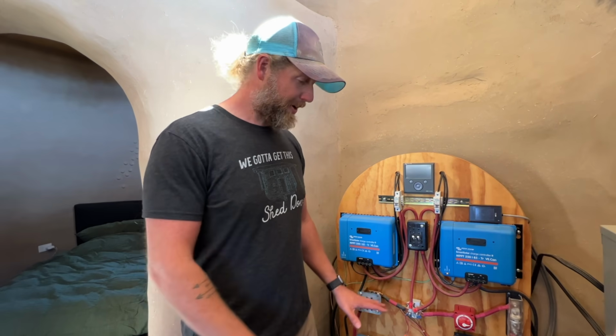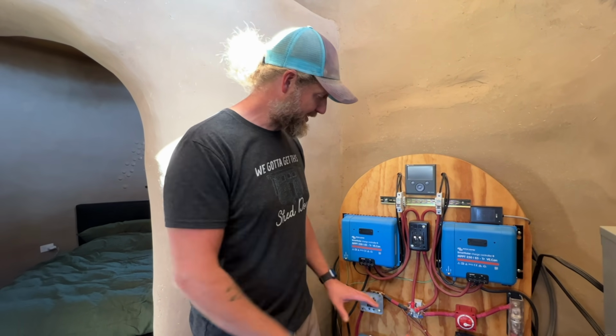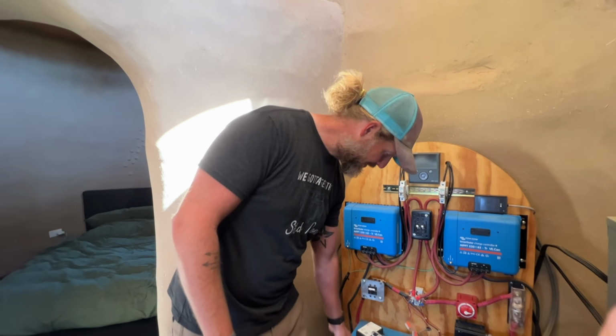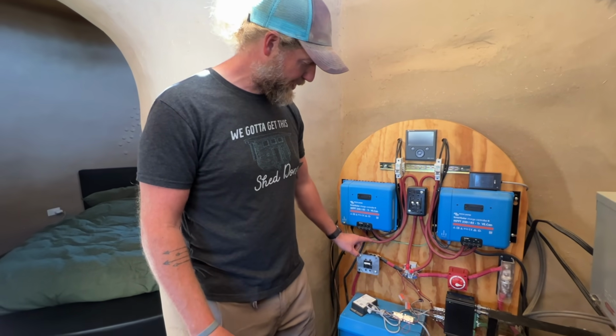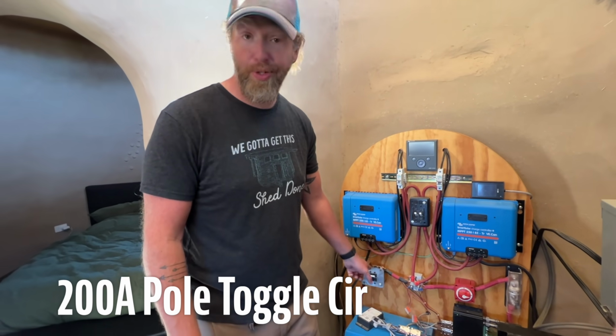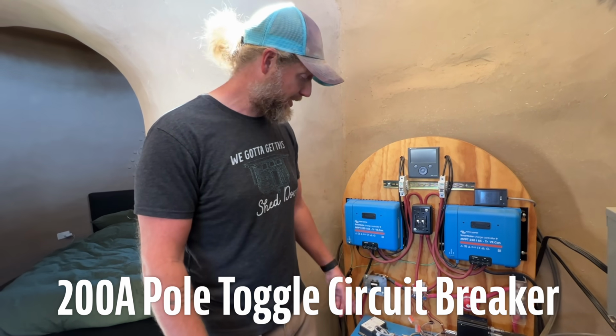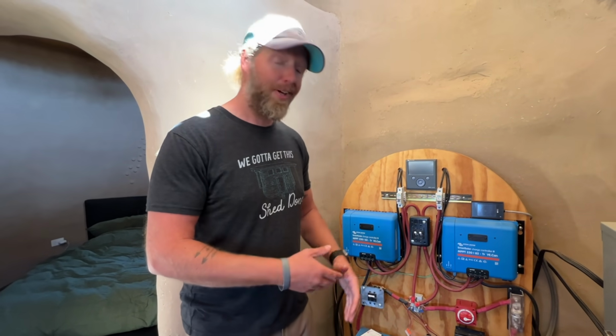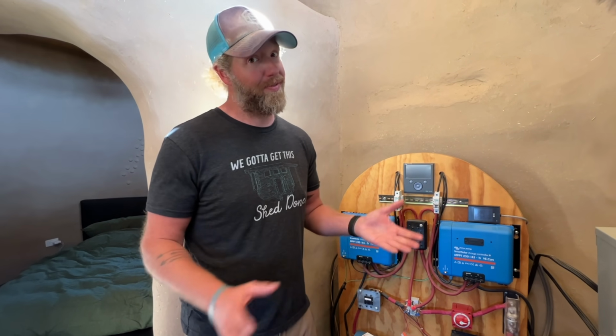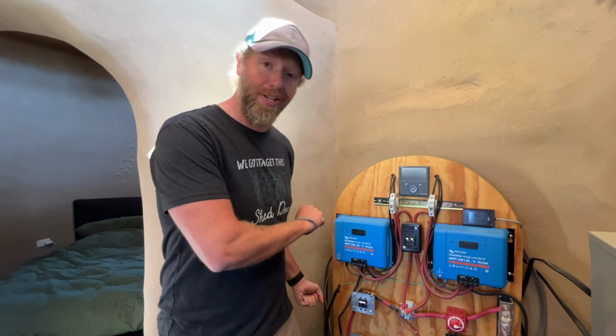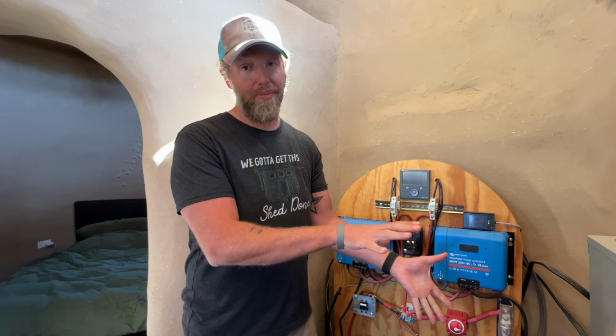The last major part of the 120 volt side is that you're going to have power coming from that contactor into your inverter. But first it's going to flow through a circuit breaker. This is a 200 amp circuit breaker. Again, we can flip this off if we want to shut power off to the inverter, but it also protects the system if the inverter decides to go haywire, so that power doesn't flow back through the system if we don't want it to.